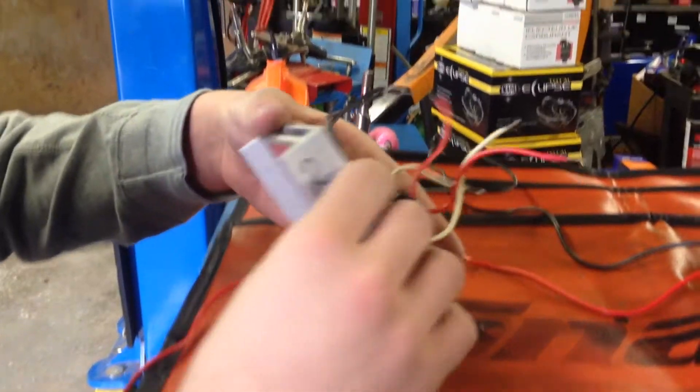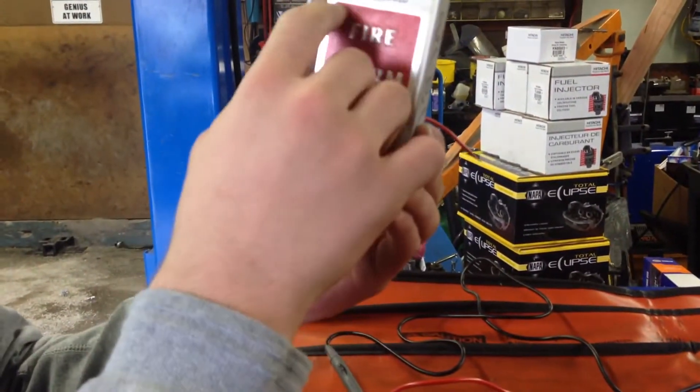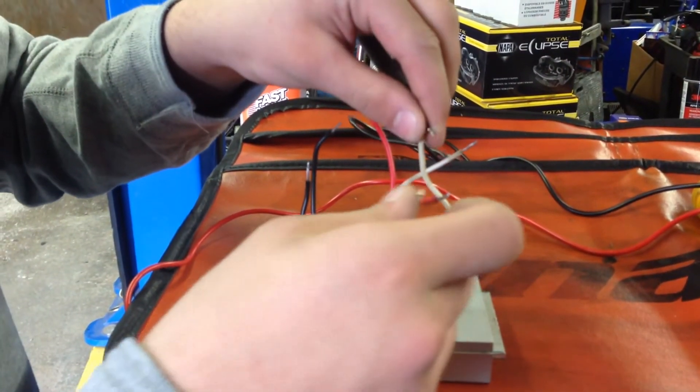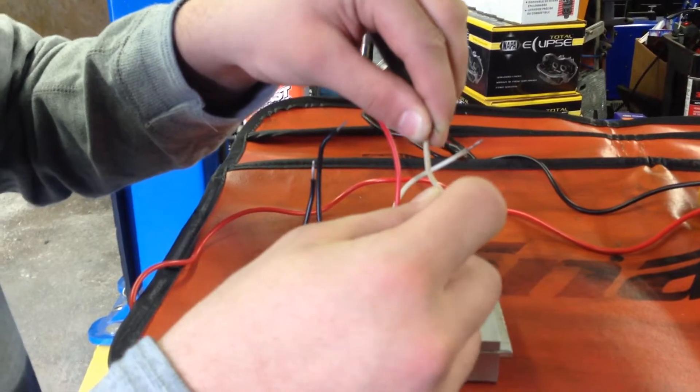Now, let's say somebody pulls the alarm. It says operated. What we're going to do is test for continuity on the whites. And there's continuity. It's a positive 24 volts.